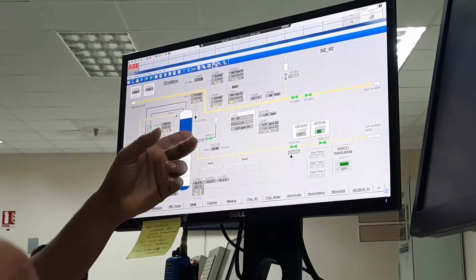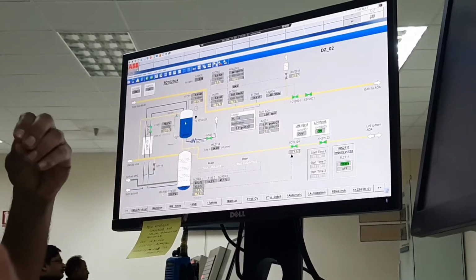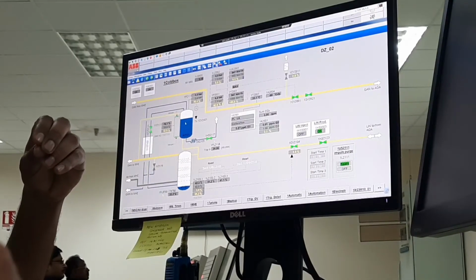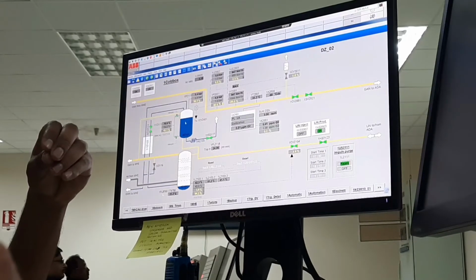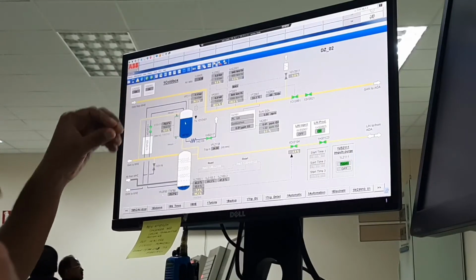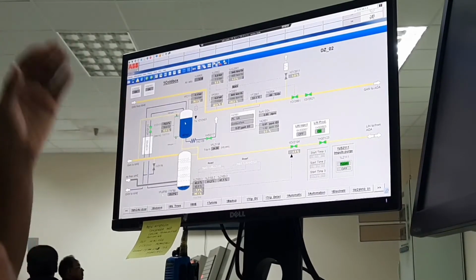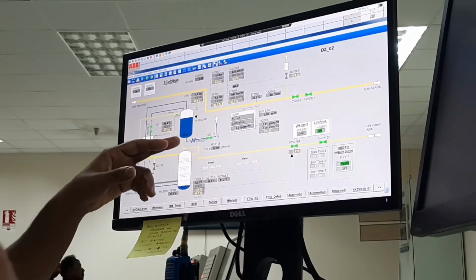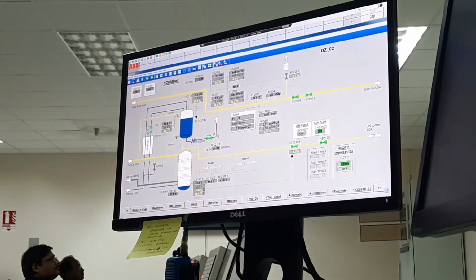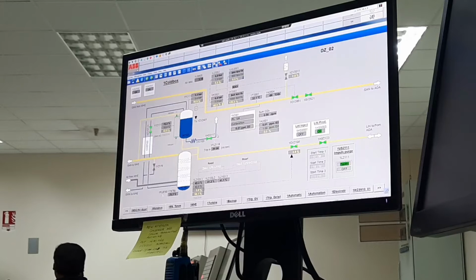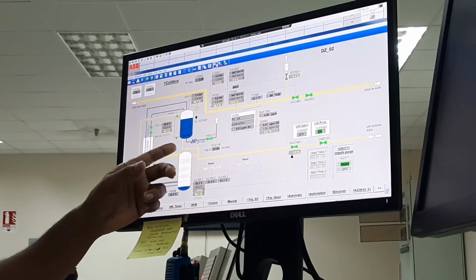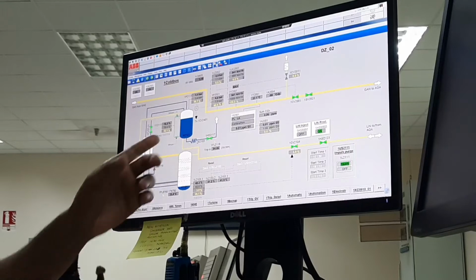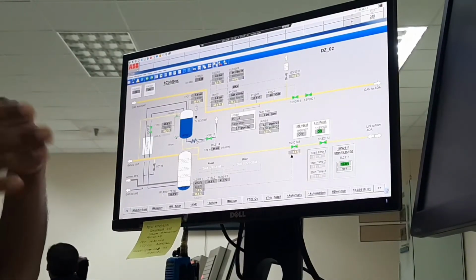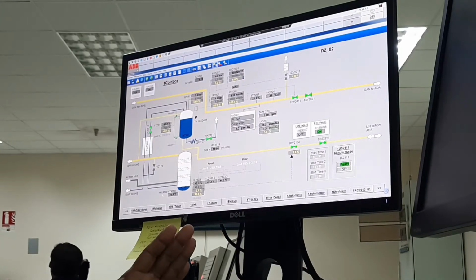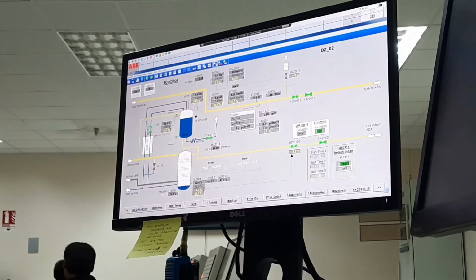Why this line? Because in this vessel there is a possibility of some oxygen. If oxygen and this CO2 are available in this vessel, level fluctuation is possible. For removing the fluctuation, we are giving one vent line. This is the vent line. Some liquid passes continuously, with a flow meter. We are also using this line for the compressor, like flushing, because of contact with air and the atmosphere. Okay, clear? After, if you have any question you can ask me, no problem. I will try to give an answer.